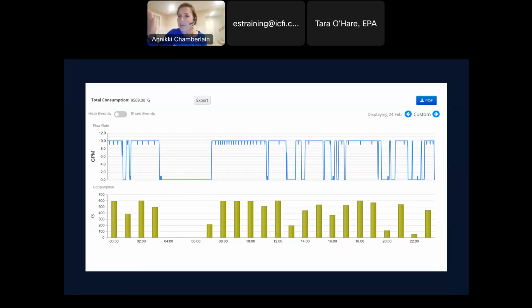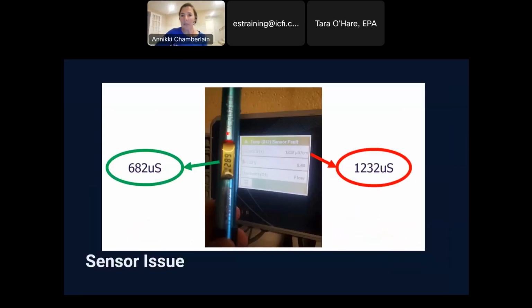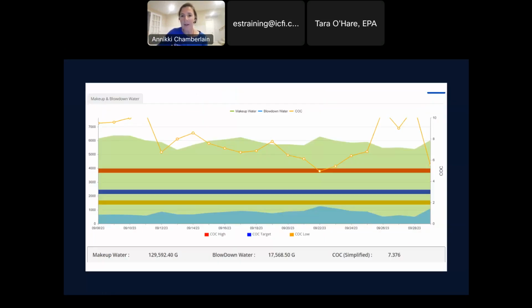So what does it have to be? The sensor. I was able to go to the site and verify this is the conductivity reading from their tower, reading at 1,232 microsiemens. My sensor, which I always carry a standard with me so I can verify my conductivity pen is working correctly, is 682. So basically their sensor was reading twice as high. Probably just a miscalibration, but that was causing it to blow down constantly. So that's a water waste event that we were able to capture.